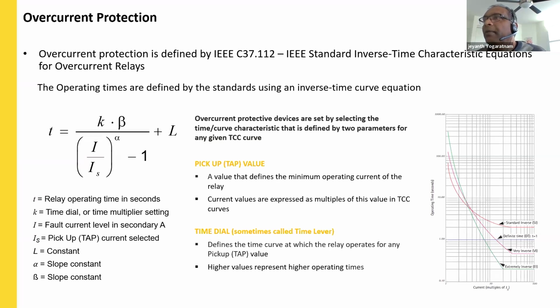So when it comes to the time overcurrent curve setting, there are two parameters that need to be set. One is the pickup setting. For the phase time overcurrent element, the pickup is set roughly around 1.3 to 1.5 times the maximum feeder load. In addition to that, for the ground overcurrent or neutral time overcurrent elements, the rule of thumb is to set 25 to 30% of the load current. We have to make sure that whatever the pickup is set to, it should be able to override the maximum unbalanced current seen by the system during normal operation.